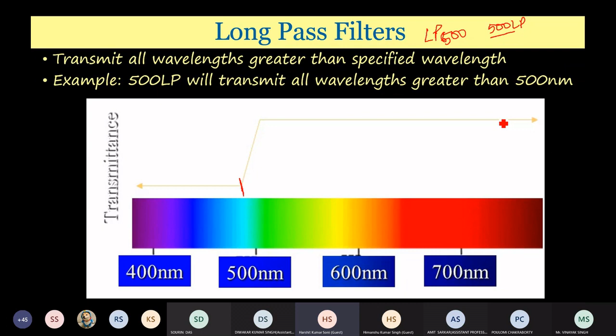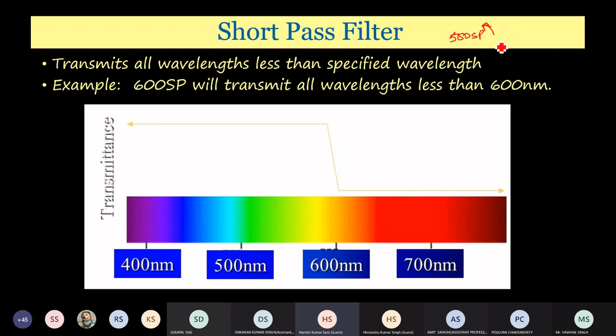The opposite is the short pass filter. It will allow everything which is shorter than that. It transmits all the wavelengths which are less than the specified wavelength. Here I had given the 600 short pass example. It is written 600 SP, 600 short pass, which means it will allow all wavelengths lower than 600 nanometer. If it is written 500 short pass, it will allow everything below 500, and everything above 500 will be stopped.